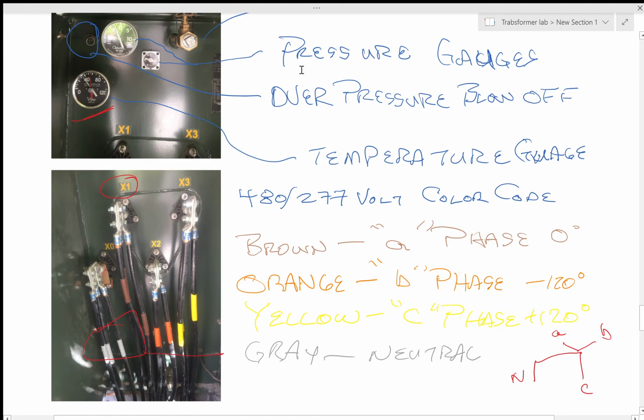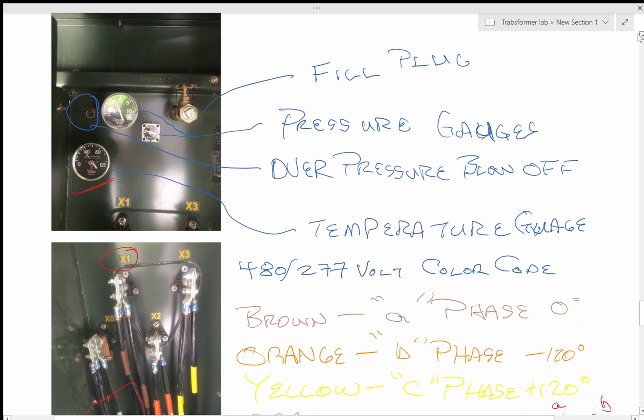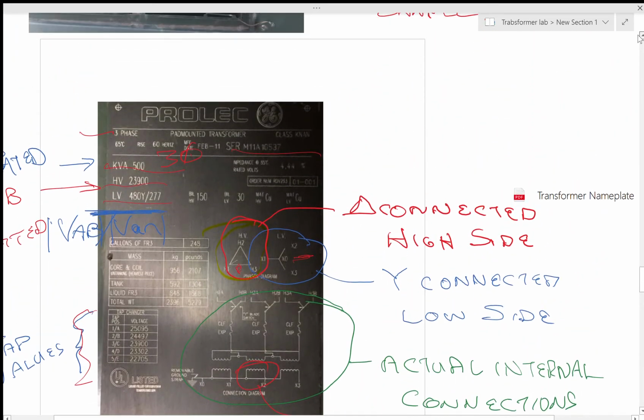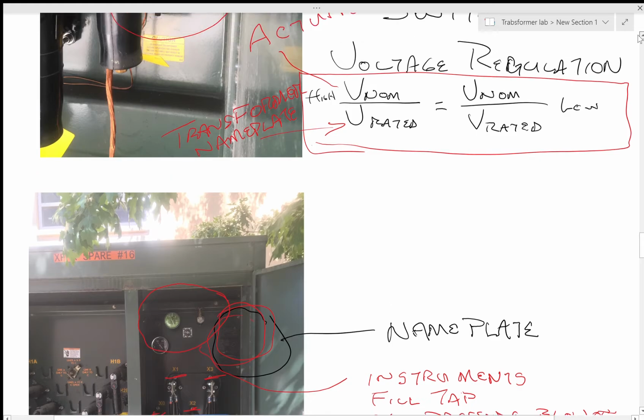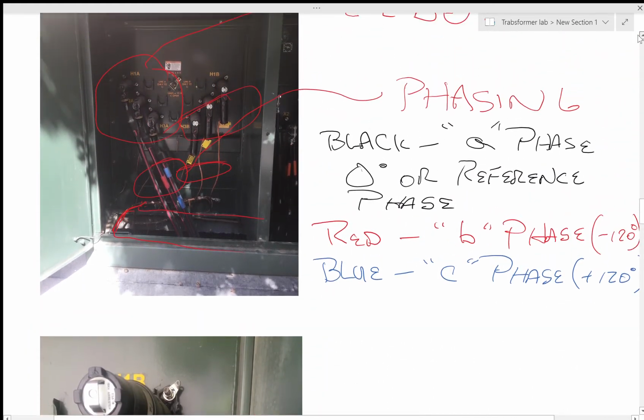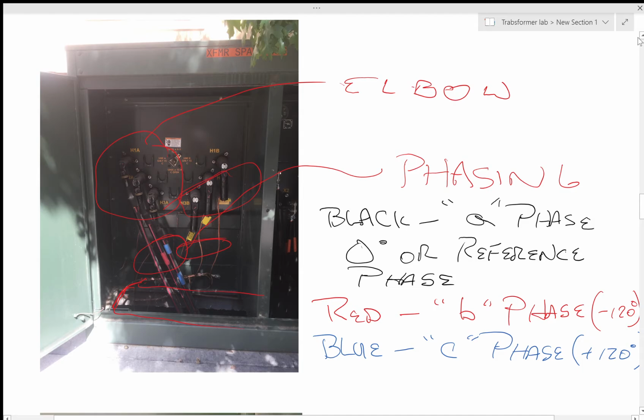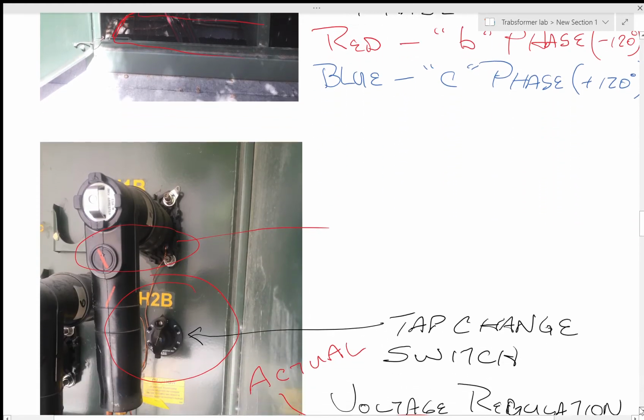So if you go back, let's see if we can see this. Let me see if I had this down. Yeah, there you go. Notice there's no X0 or H0 phase in here. If this was a Y-connected transformer, it would have an H0 phase for a neutral. Typically, in most high sides, they don't use Y. They can. They usually just ground that X0. They don't put an actual neutral on it, for the most part, as a general statement. Some people do, some people don't. Okay.